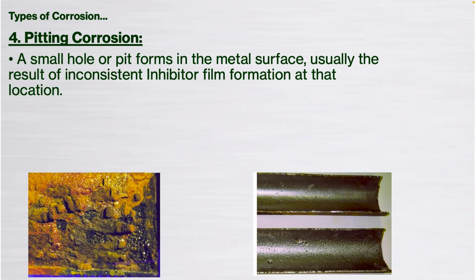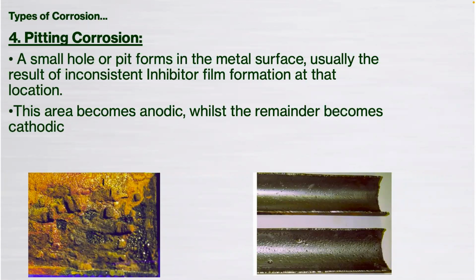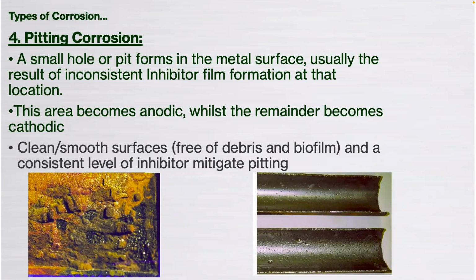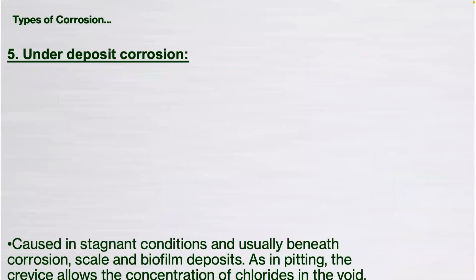Usually we've not had a good level of inhibitor laid down. So it could be that you haven't monitored, or the site hasn't monitored the inhibitor levels. They're not maintaining optimum inhibitor levels. It could be that the pipework basically isn't very clean, or it could be biofilm that's laid down as well. So the area becomes anodic at that location, whilst the remainder becomes cathodic. So you need to be free of debris and biofilm, and certainly, as I say, a consistent level of inhibitor.